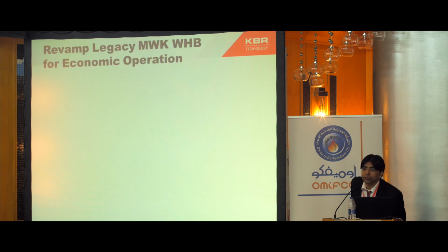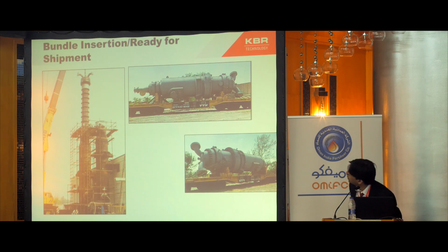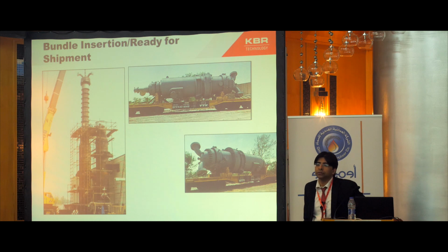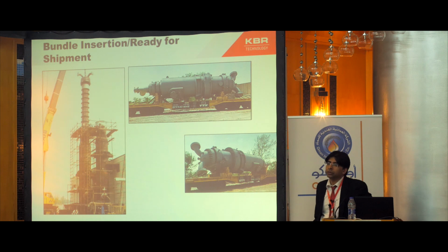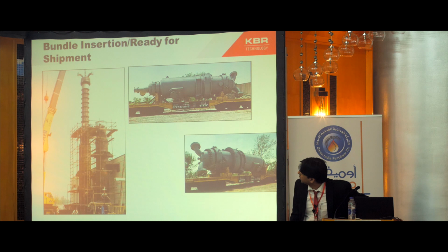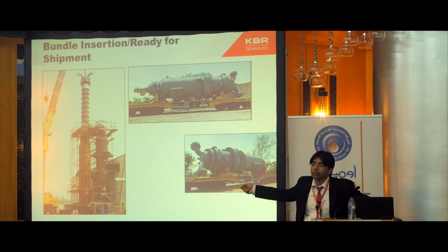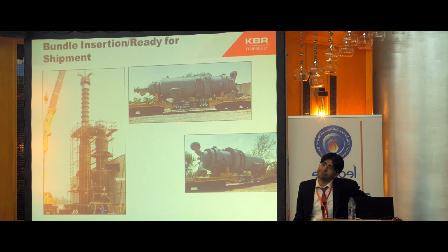May I ask a question? Yes, please. When you pull out the bundle outside and bring it back, the bigger flange now becomes bigger because instead of having a shroud, you increase the diameter, of course. Yes. Then the head flange will be bigger. At the one which is smaller than this one, we're having a headache reassembling these two flanges. We need very big hydraulic jet spanners. Do you find a way to keep connecting the two flanges with the top tube sheets easy?